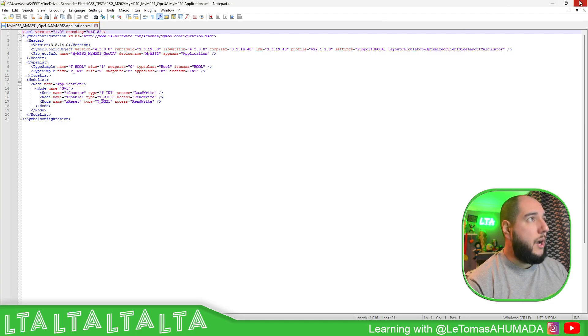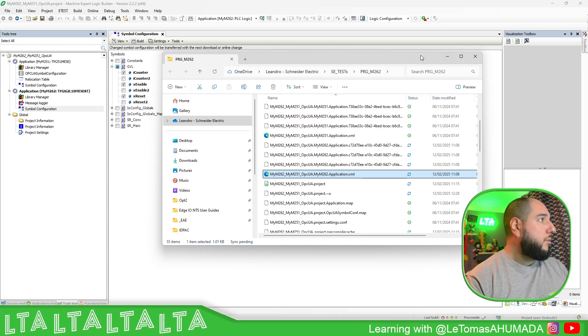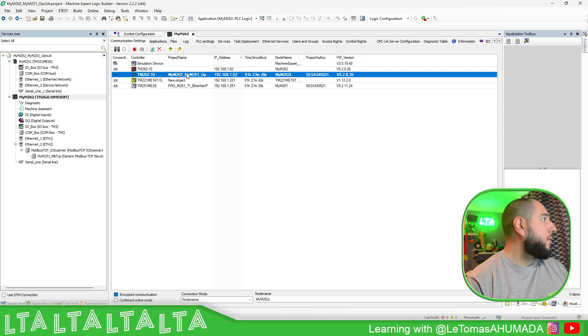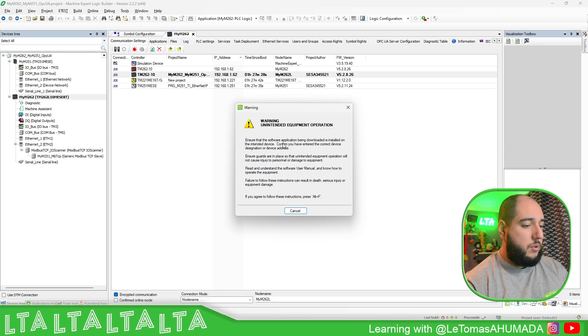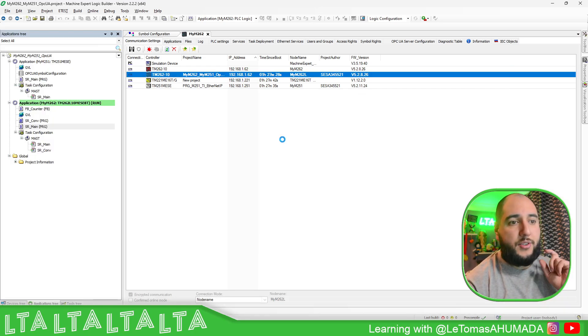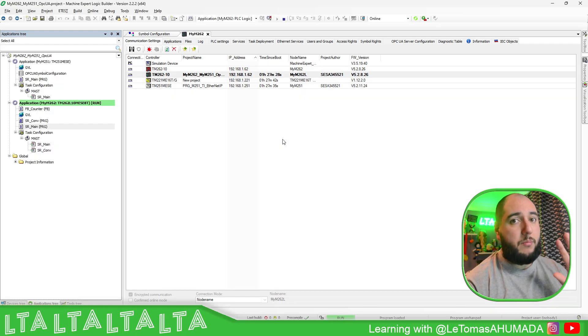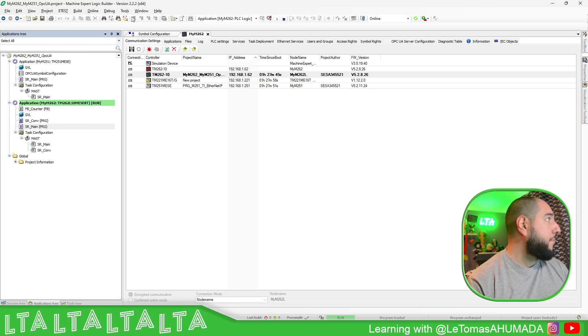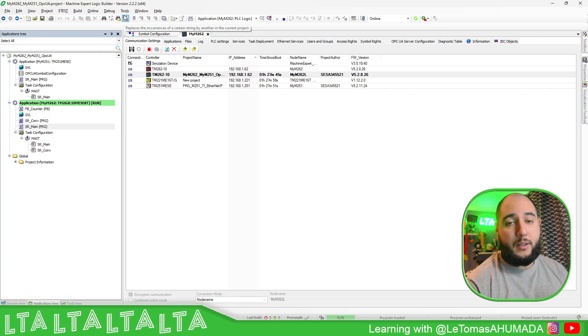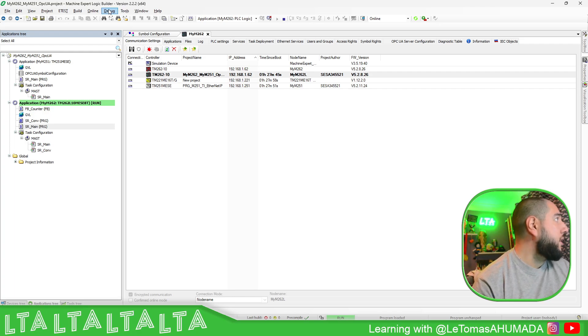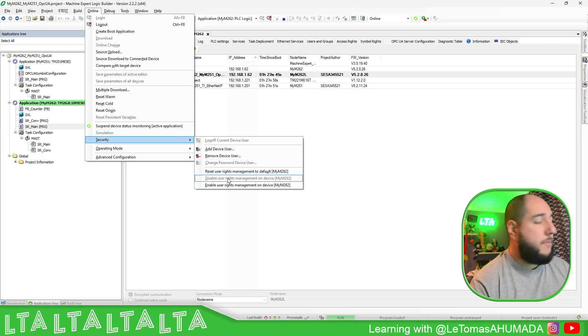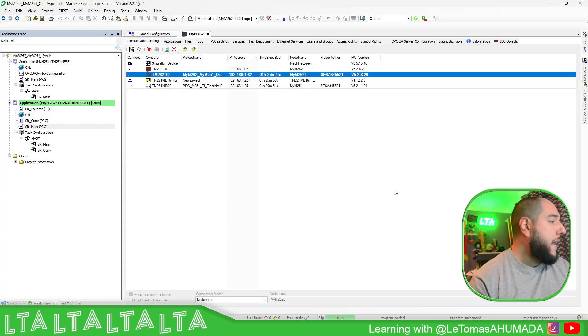The XML file will show the values that you have. Once you have done this and connected to the controller, something very important we need to double-check is if the controller has security on it. We need to disable that for this particular process. If you're trying to log in and it asks you for a password, we need to disable that. So here: Security, Disable User Rights — and that will disable the user rights.